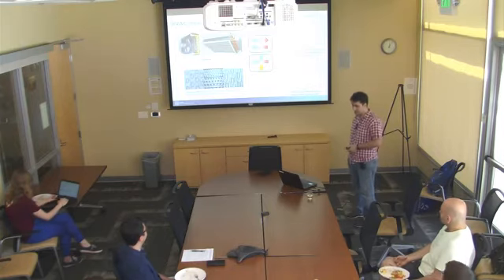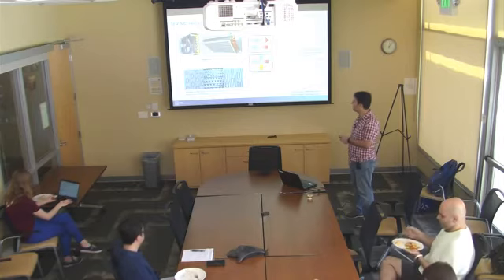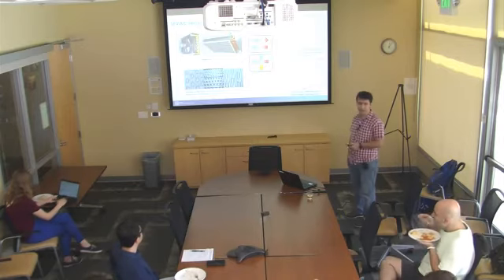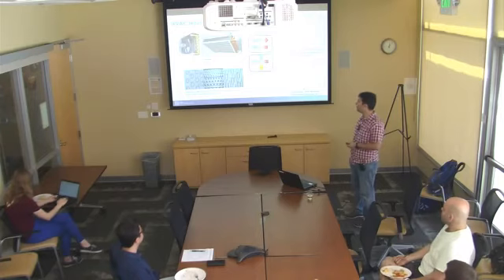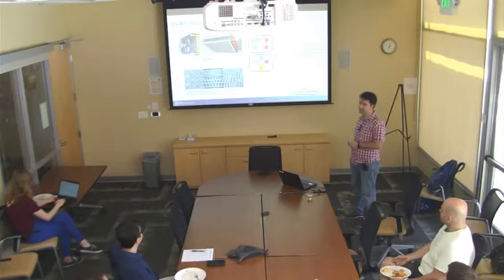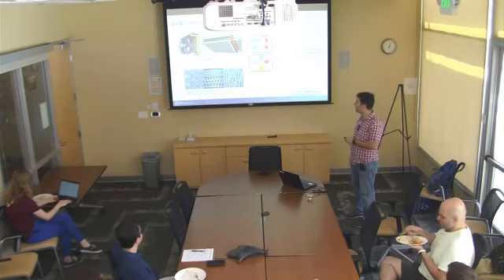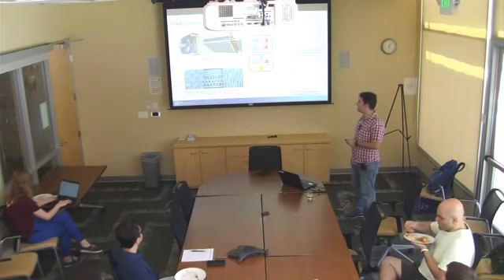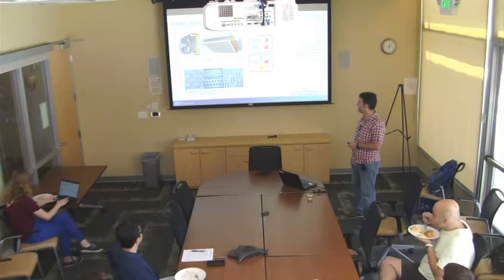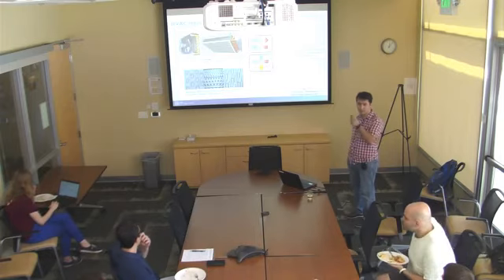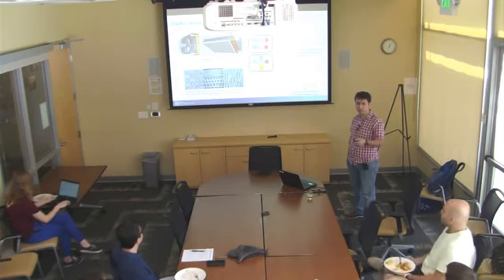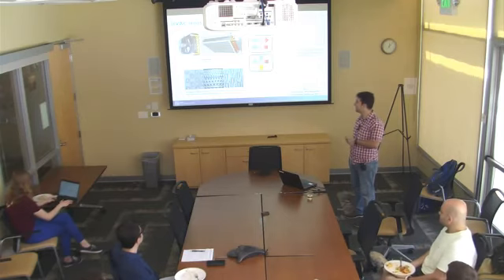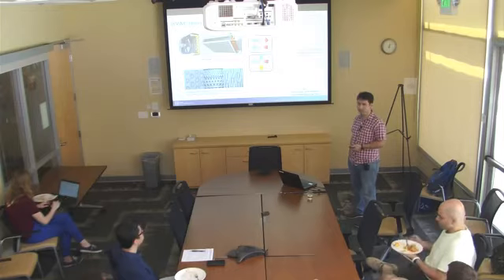your efficiency. So on the left, we have pictures showing how these conventional air handler units, or heat exchangers for transferring heat between water and air, are built. They are essentially tubes bent in the shape of a coil that makes several passes of the tube as the flow of air passes across them. And there is a fan that blows or sucks the air through these tubes. If we have more layers of these tubes, we have more heat load, or capacity, in this heat exchanger, but there is a higher pressure drop in the air handler.